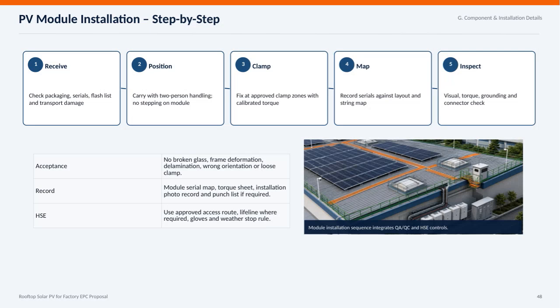Let's walk through the step-by-step process for PV module installation, focusing on the key components and installation details. First, when we receive the modules, it's essential to check the packaging, verify serial numbers against the flash list, and inspect for any transport damage. Always handle the modules carefully during positioning, ensuring two-person handling and never stepping on the modules to prevent damage. Next, the modules are clamped securely at approved clamp zones using calibrated torque to maintain structural integrity. After clamping, we map the modules by recording their serial numbers against the layout and string map, which is crucial for tracking and future maintenance.